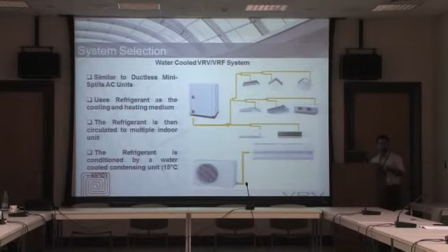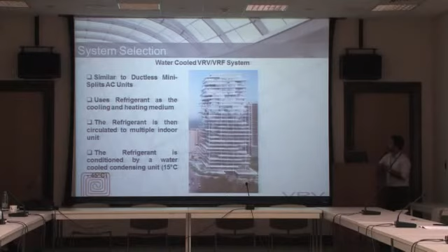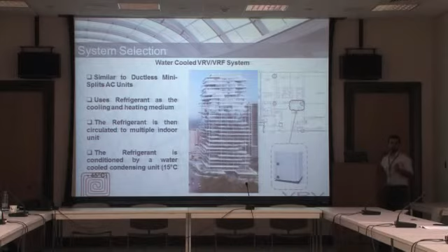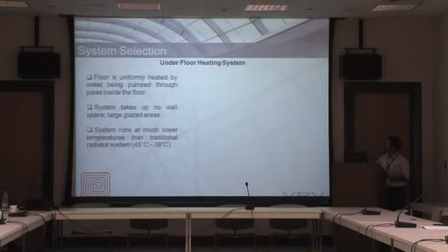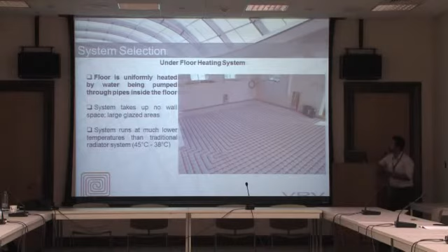The difference with water-cooled VRV is you can cool it using conditioned water at temperatures ranging between 15 to 45 degrees. We took a utility room from the architect and placed the water-cooled VRV inside the apartment. So there's nothing exposed on the elevation or outside. As for the underfloor heating system, heating is uniform. The floor is uniformly heated by heated pipes. The system takes up no wall space, and runs at much lower temperatures. Supply temperature of 45 and return temperature of 38.